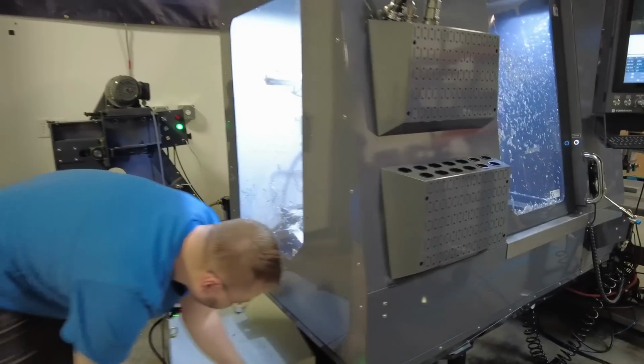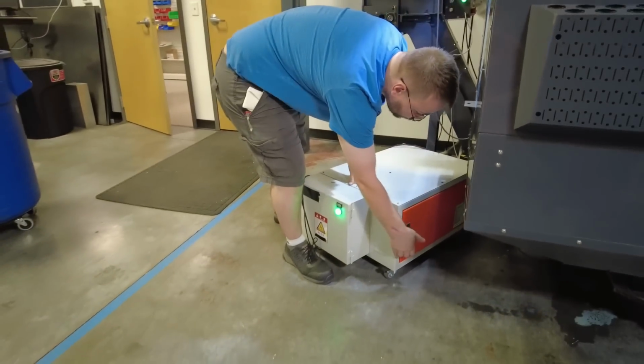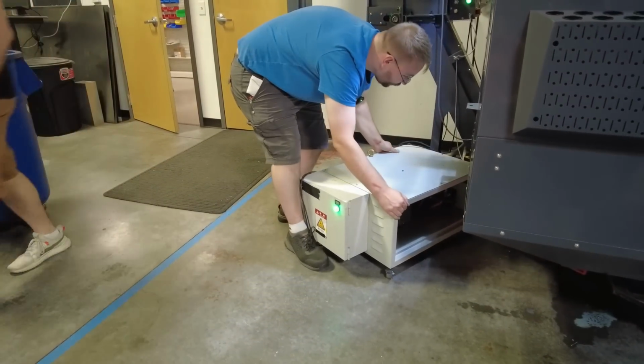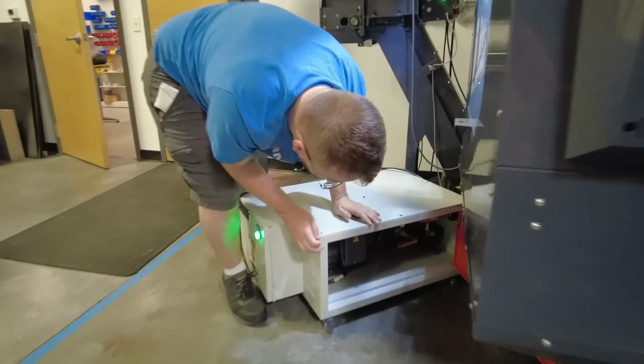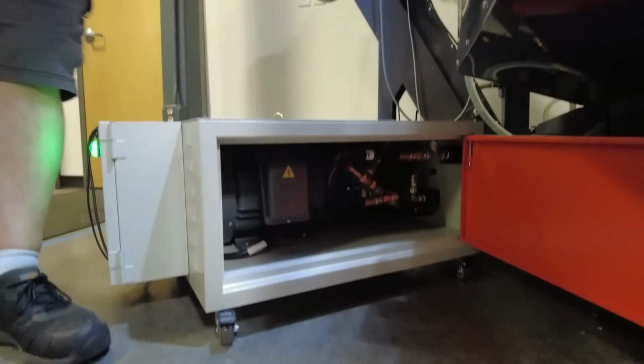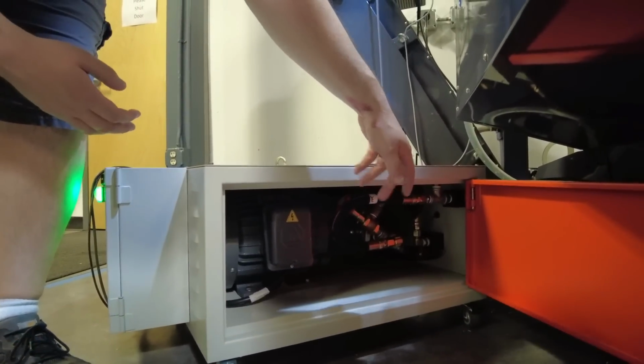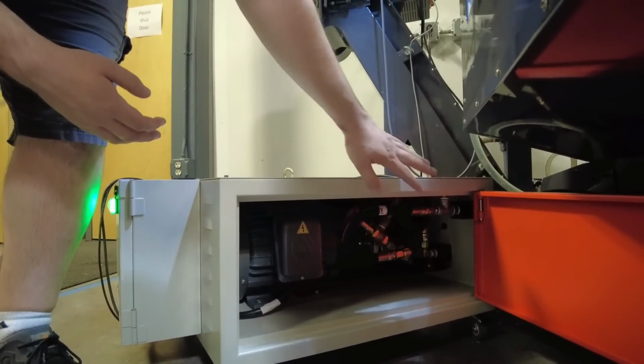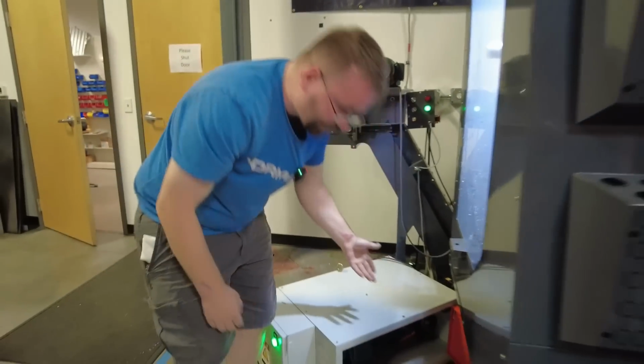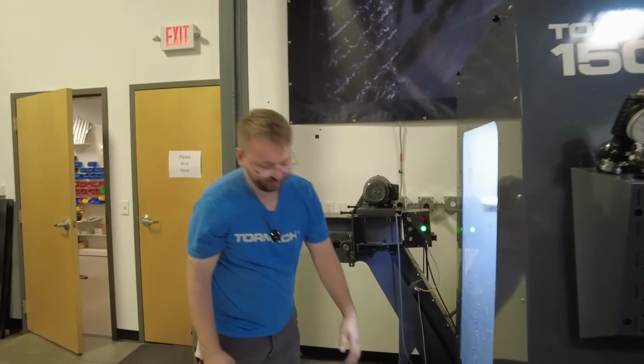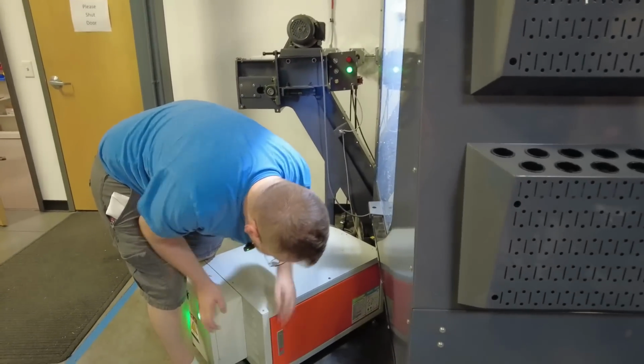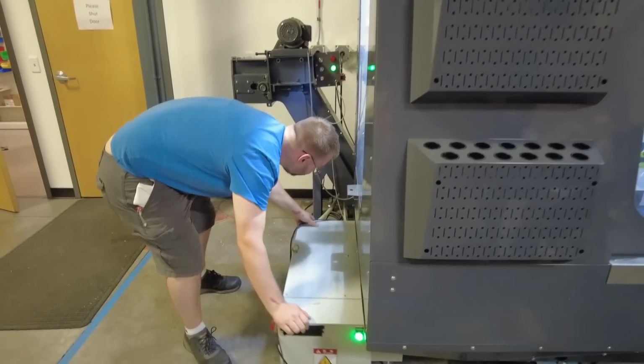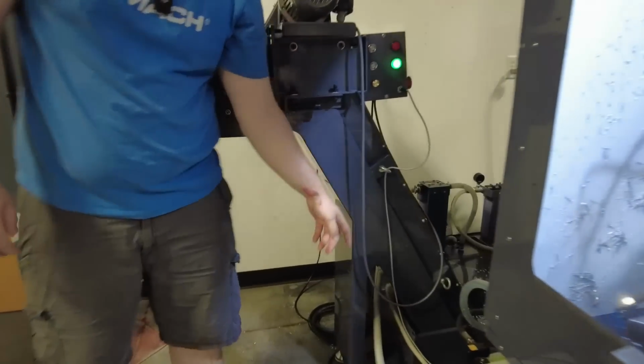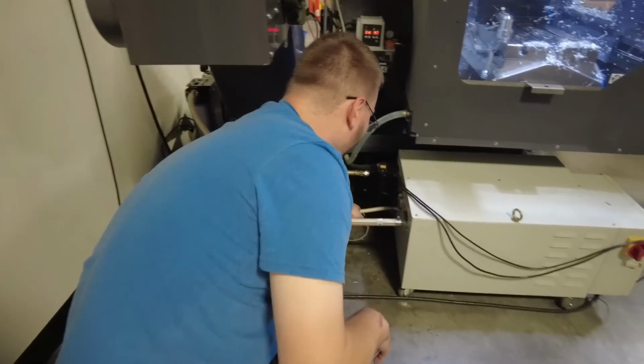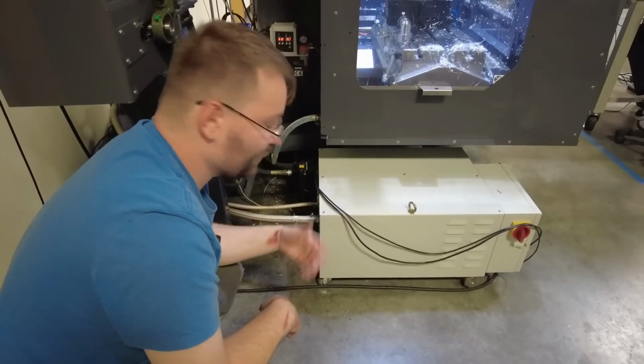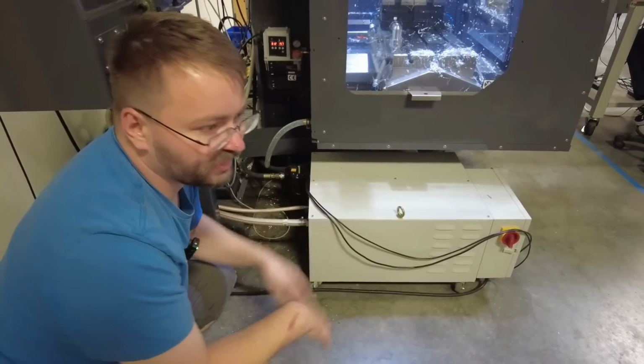For our flood coolant system, we can show the pump a little bit. Fairly dark in there, but this is a 400 PSI system. We've got just our standard electric motor, and then it's a gear pump on there. A couple pressure sensors as well to make sure that we do have pressure when we command it on, but also that we're not spiking the pressure from deadheading the pump. But if we do deadhead the pump, we have a bypass line, this guy right here, where any excess pressure over whatever we have the set point at will just be dumped back to the tank, so it's not going to blow up the system.